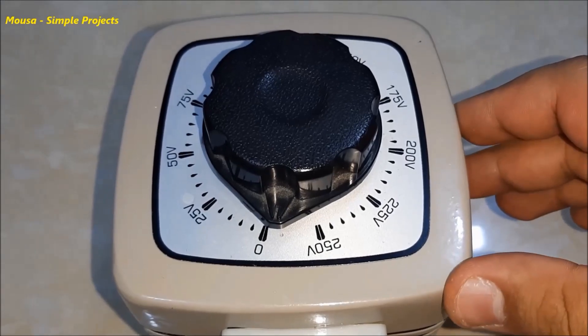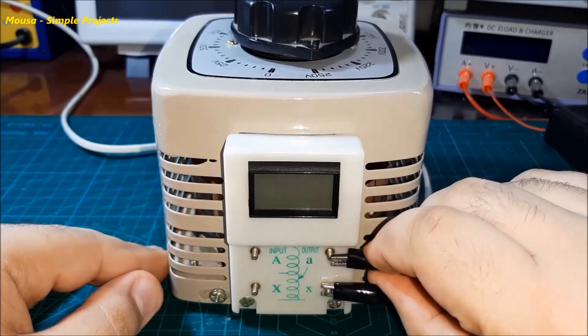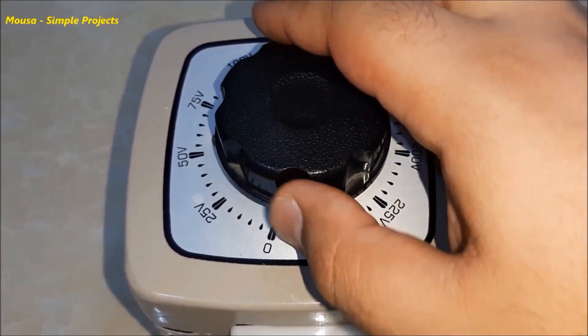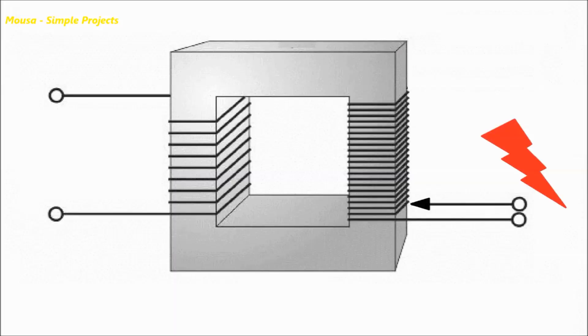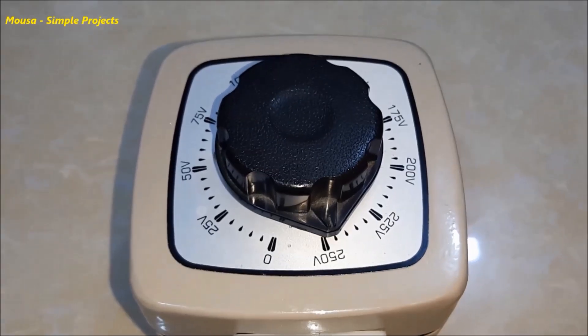There is a very important note here. When you want to connect the mains voltage at the output side of the transformer, make sure that the knob voltage selector is not on zero volts. Because in that case, you short out the mains voltage. Just put it at the maximum voltage for the first test.